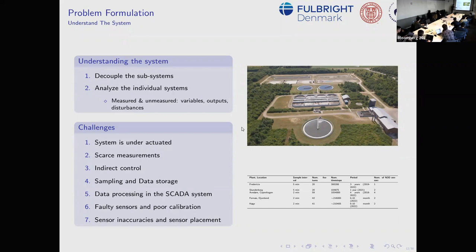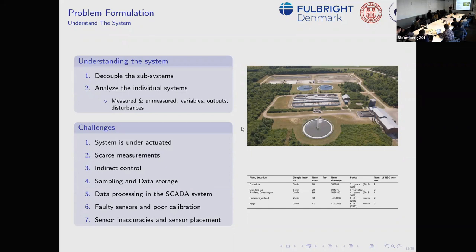Other issues include faulty sensors, poor calibration, inaccuracies, and sensor placement. Often the sensors are positioned at the effluent — where output is checked — but not inside the process itself. You're controlling an enormous tank with liquid and bacterial colonies that may vary in different areas, but you measure at maybe one place, so you're approximating what's in there.